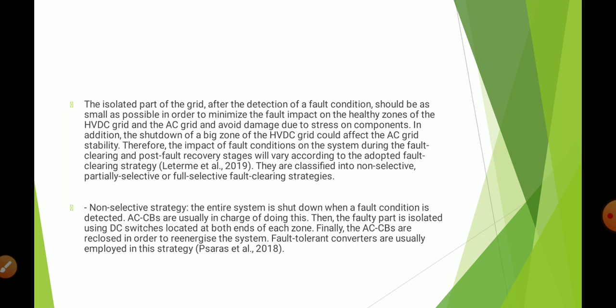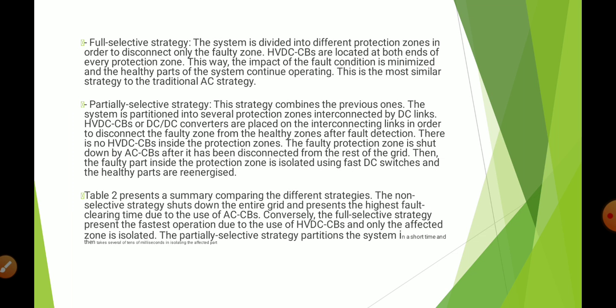Non-selective strategy. The entire system is shut down when a fault condition is detected. This is not a good strategy because when there is a fault, the entire system gets shut down, and AC circuit breakers are in charge of doing this. Then the faulty part is isolated using DC switches located at both ends of each zone. Finally, the AC circuit breakers are reclosed in order to energize the system. Fault tolerant converters are usually employed in this strategy.